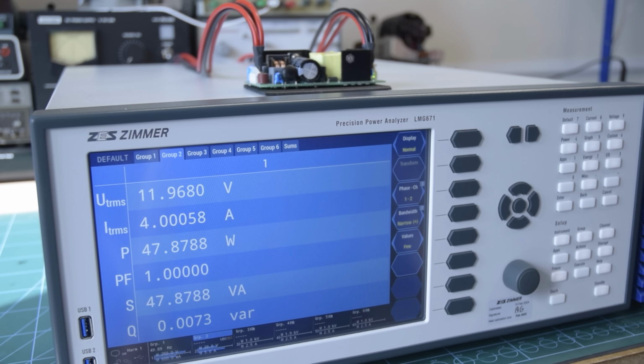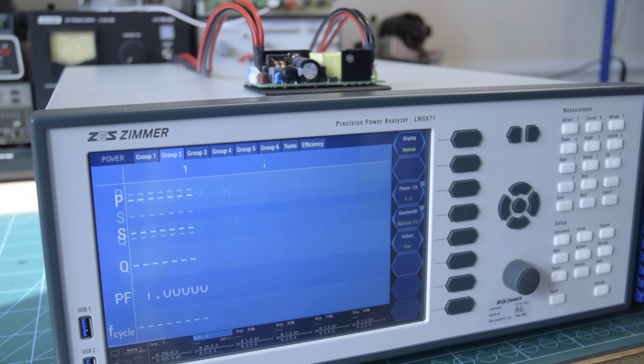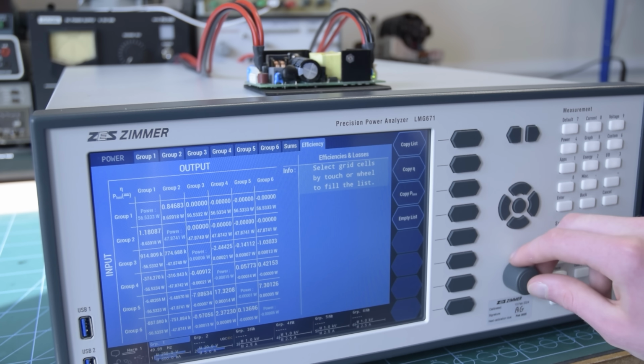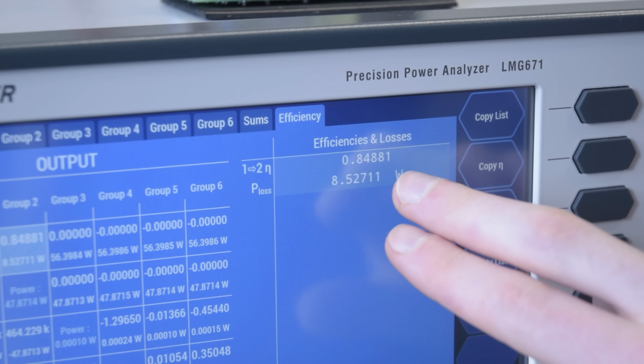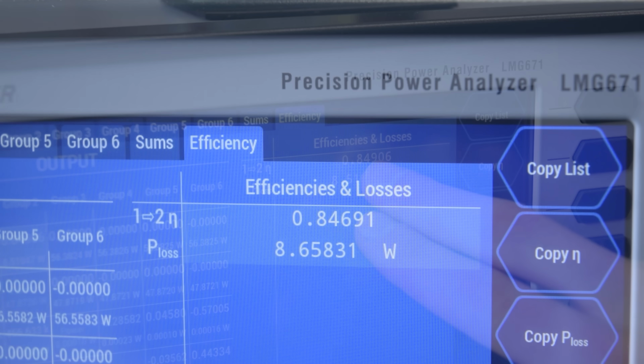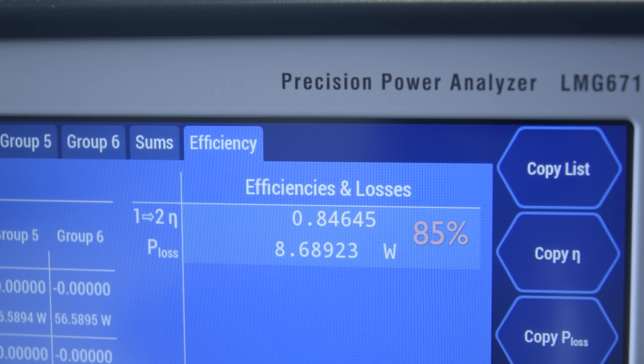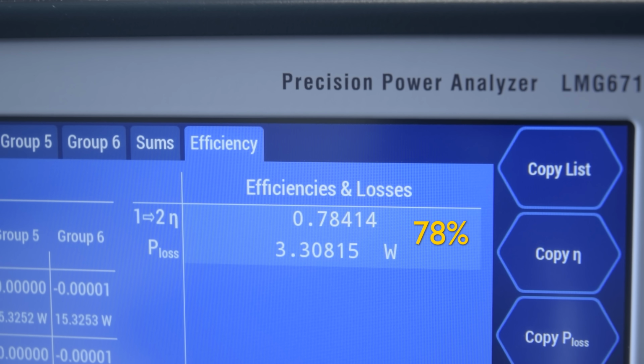The main thing we want to measure with this power analyzer is efficiency, and we can get that by clicking on this button, then a few more buttons. So you can see here we've got the efficiency, which is 0.85, meaning 85%, and the losses about 8.5 watts. These vary as I change the load. Right now I'm drawing 4 amps. If I drop that down to 1 amp, you can see our efficiency goes down quite a bit. We're now at about 78%, and our losses have also gone down.